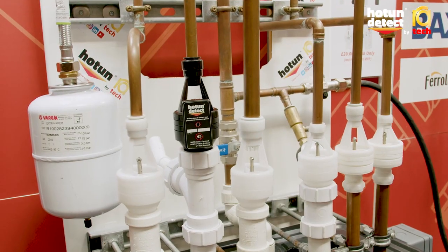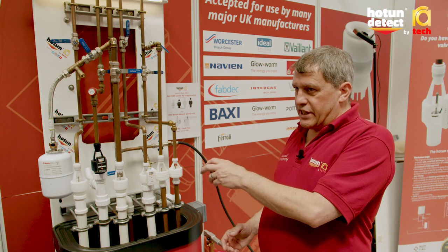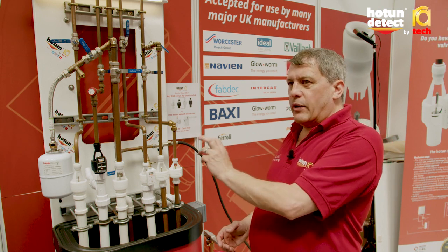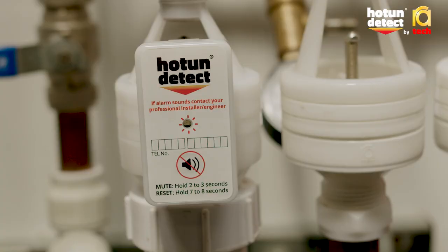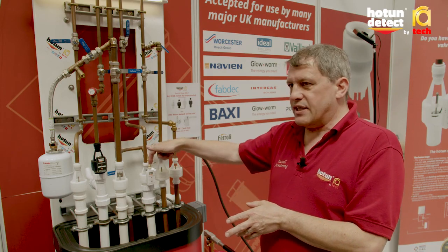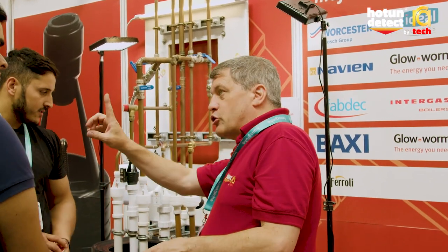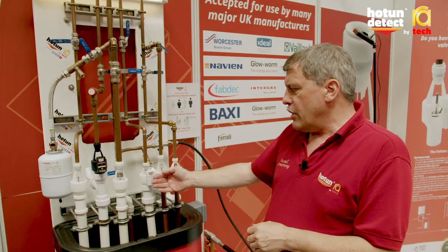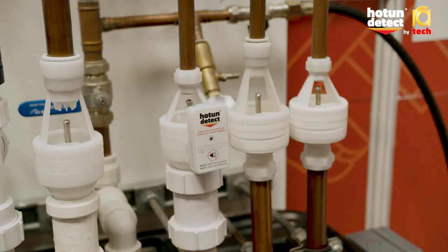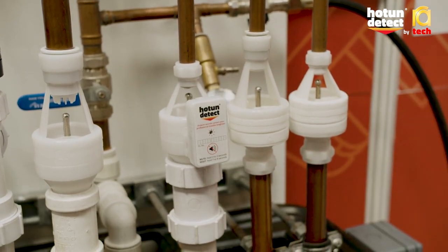We can manually mute by pressing and holding for three seconds, and that's muted for 24 hours. It's also got an auto mute function and auto reset. After the alarm has been going off for 12 hours it mutes itself for 24 hours. After 24 hours, if the sensor tip is still wet it sounds the alarm again. If the sensor tip is dry it resets itself into what I call active standby — you know the unit is in active standby because it has a green flashing light every seven seconds, a visual indication that the unit is active.